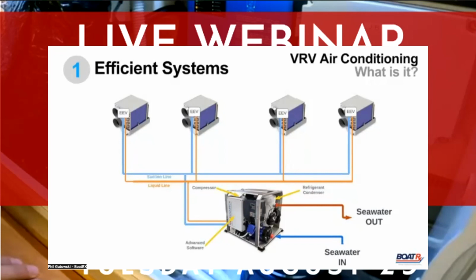So if you look at this diagram, the refrigerant in the system starts its journey in the compressor, which squashes it down to make it a really high pressure, really hot gas. And that refrigerant then travels to the condenser, and that's where it interfaces with seawater in the heat exchanger, and the seawater takes the heat away from the high pressure, high temperature gas and actually condenses it down into a high pressure liquid.